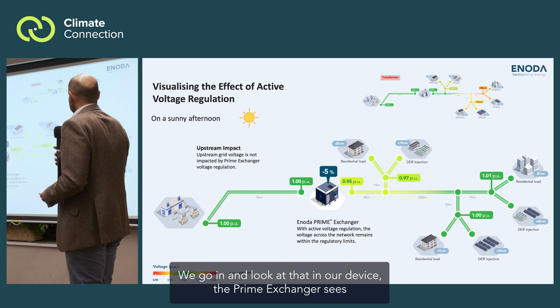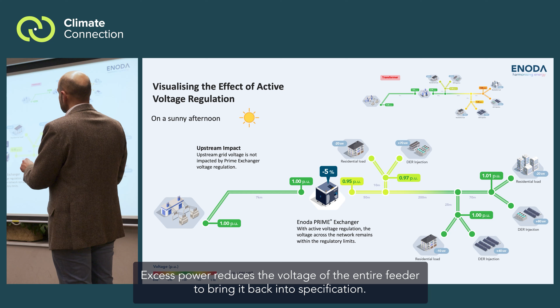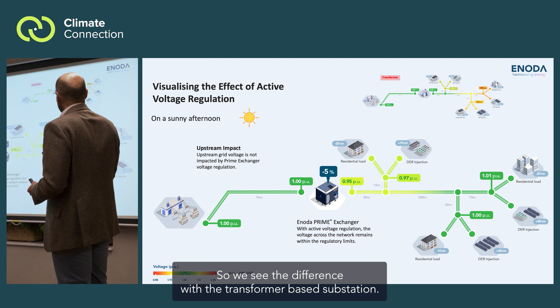We go in and look at that, and our device, the prime exchanger, sees that it has this excess voltage at the bottom of the network. Excess power reduces the voltage of the entire feeder to bring it back into specification. So we see the difference with the transformer-based substation.